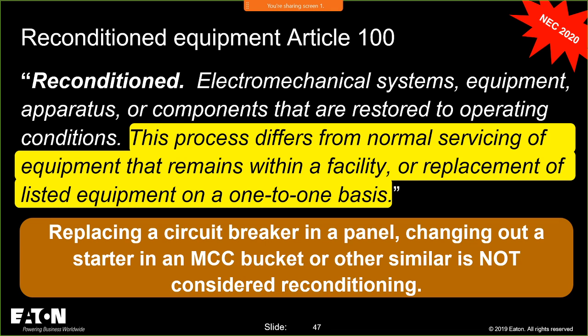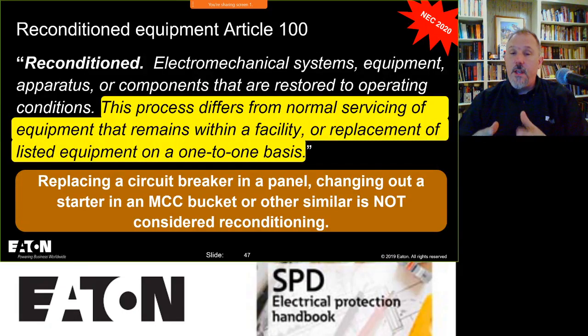So, for example, if I'm going to take a circuit breaker and follow the manufacturer's instructions to install or make a change that's part of that listing and part of the manufacturer's instructions, I'm doing something that is normal servicing. If, for example, I have a motor starter inside a motor control center, and for some reason the motor starter fails, then I'm going to replace that motor starter. I take the motor starter out, I have a brand new one, I put it in. I have replaced a component one for one inside a bucket, inside an MCC. That would fall into replacement of listed equipment on a one-to-one basis.